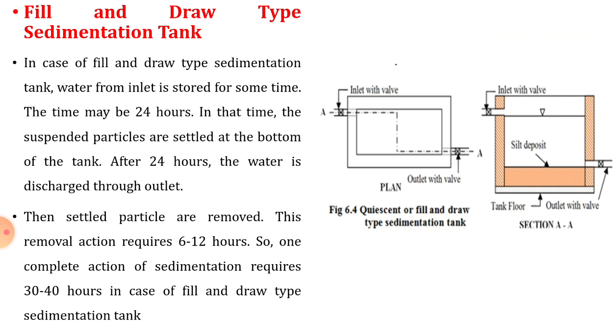First, based on the process, it is a fill and draw type sedimentation tank. If you see the figure, it is a rectangular sedimentation tank. In this, first of all, the entire tank is filled up with the wastewater. Then sufficient detention time is provided so that the suspended particles present in the wastewater start settling due to reduction in the velocity. In case of fill and draw type sedimentation tank, water from the inlet is stored for some time.